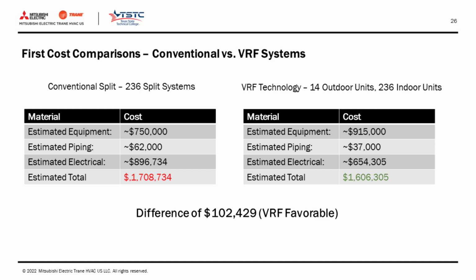Now, compare that to the VRF side, and there is no electric heat needed. Only a single 15 amp breaker, and again, depending on line length, number 10 or number 12 wire size. So looking to these details together, even with the higher price of the VRF equipment, it's still a better decision to go with VRF.